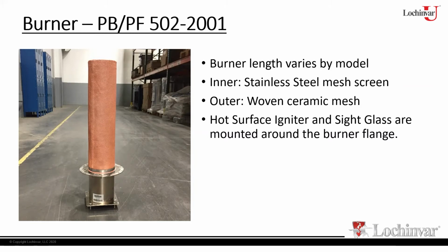Under normal operating conditions, the flame never really touches the burner surface, right? The flame is always pushed off the burner surface. It stays away from it. This is where the run cool technology that we talk about comes in. If you've ever been to the factory, you've done the factory tour, you've seen the burner demonstration in our lab. If you've not had that chance, hopefully someday soon we'll be able to start inviting people back to the factory, and you can come and see this burner demonstration for yourself.